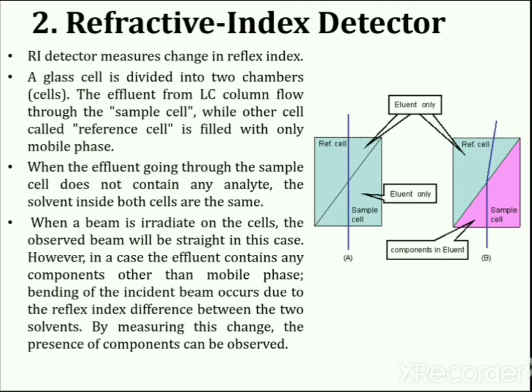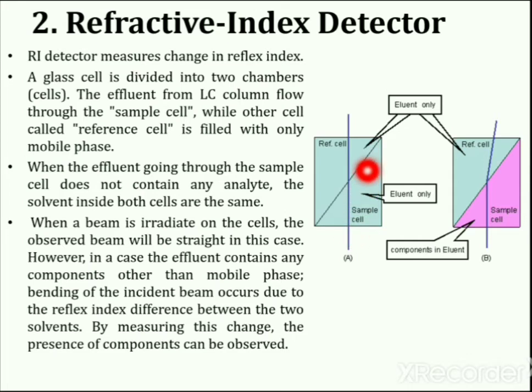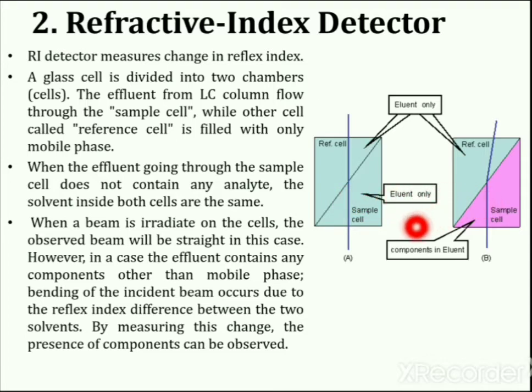The next detector is the refractive index detector. It measures changes in refractive index. This type of detector contains a glass cell which is divided into two chambers or cells. The eluent flowing from the liquid chromatography column flows through the sample cell, while the other cell, called the reference cell, is filled with only mobile phase. When the eluent going through the sample cell does not contain any analyte, the solvent inside both cells is the same.